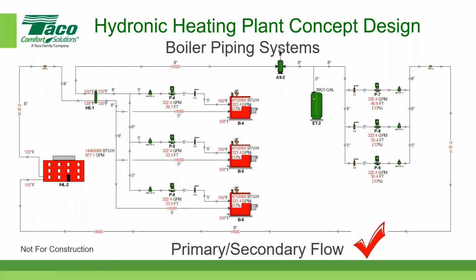So in this case, I like the primary secondary system. Sometimes we refer to it as being idiot proof, and it solves a lot of problems. I will admit that in newer systems, people are considering variable primary flow for their boiler plant, but I prefer the primary secondary flow system. It's much more manageable, and it's easier to maintain, and it's easier to troubleshoot and service.